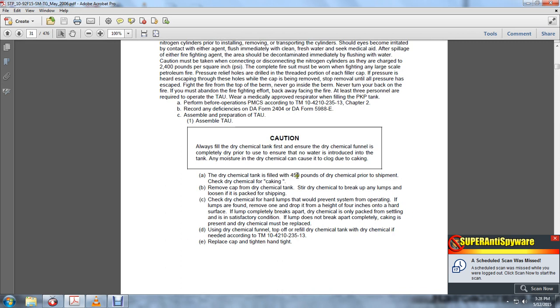A dry chemical tank is filled with 450 pounds of dry chemical. Prior to use, check the dry chemical for caking. Remove the cap from the chemical tank and stir the dry chemical to break up lumps loosened in shipping. Check for hardened lumps that would prevent the system from operating. Remove one lump and drop it from a height of 4 inches onto a hard surface.